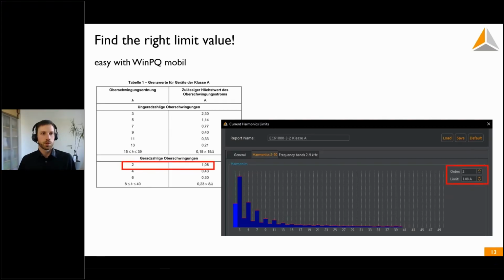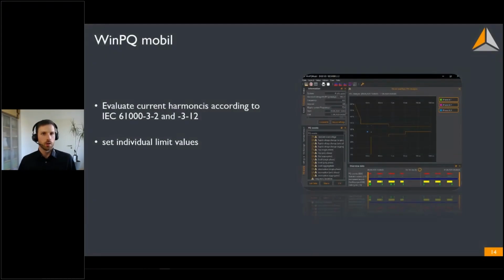So let's say, for example, harmonics of the second order are allowed to have an emission of 1.08 amps per phase. And you will find this as well in PQMobil. So second order, 1.08 amps. And this is what I'm going to show you now, to see where to find these settings and evaluation.